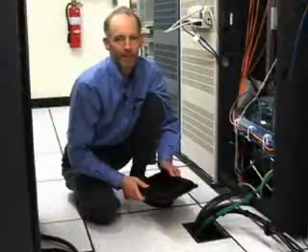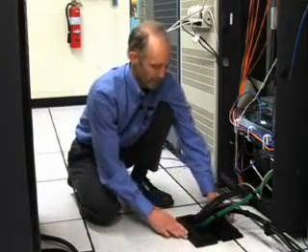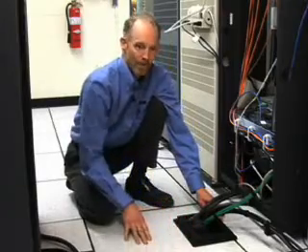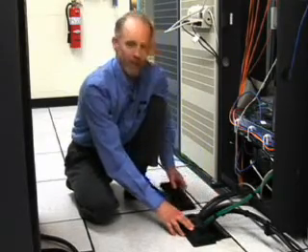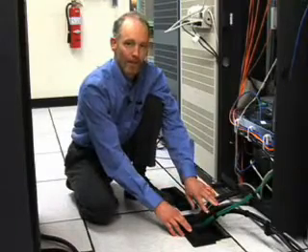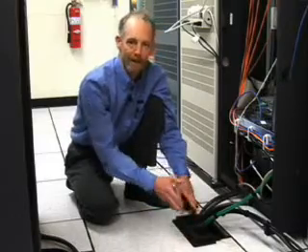The first step is to test fit the KoldLok grommet over the cable cutout. The portion of the grommet in the aisleway will be attached to the tile. The portion of the grommet behind will be removable so that the tile can be removed later without affecting the cabling. A KoldLok grommet can seal a hole seven inches by nine inches.